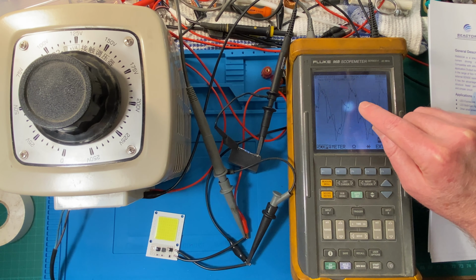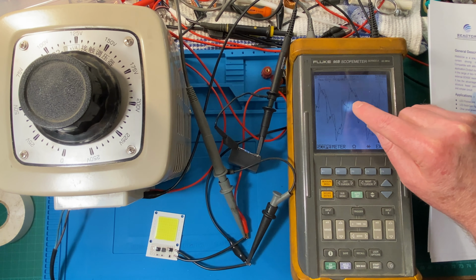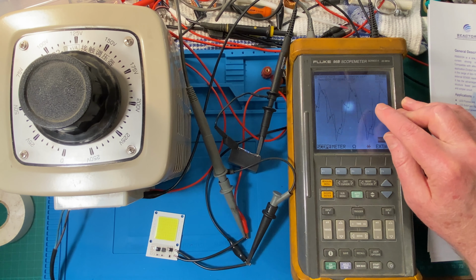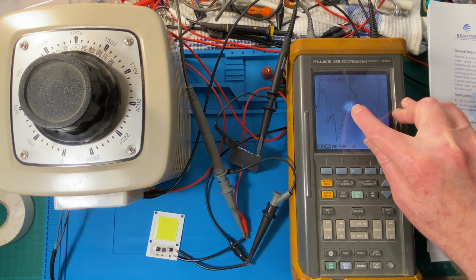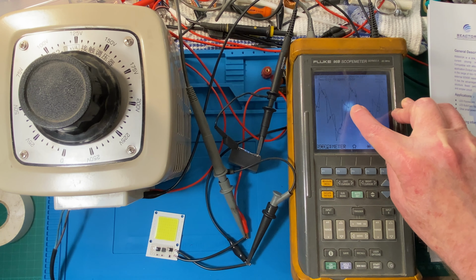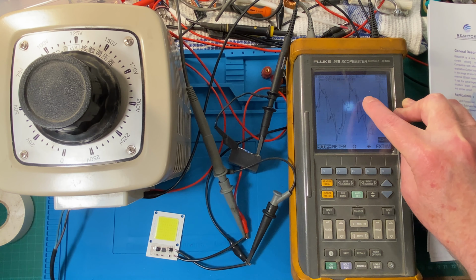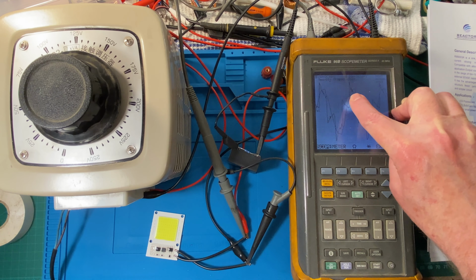So the area where current is being drawn off the mains is only this middle part. So basically you're not going to have the best harmonics or the best power factor out of it, because it's not a linear load. But that's how solid state rectifiers work, and the current's all drawn around this area after about 200 volts on the main cycle.